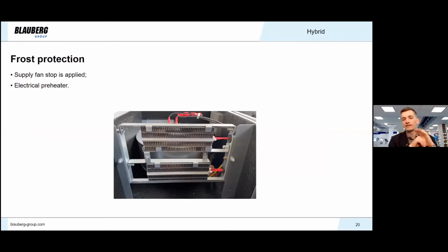The most advanced decentralized modification, the hybrid max E unit, also has an electric preheater built in. It is installed there to perform freezing protection and maintain balanced ventilation. All the rest of the modifications utilize supply fan stop to protect the heat exchanger from freezing. It is worth mentioning that both types of freezing protection guarantee normal operation of the unit down to -25. We have tested them in our climatic chamber, and test reports can be sent to you upon your request.